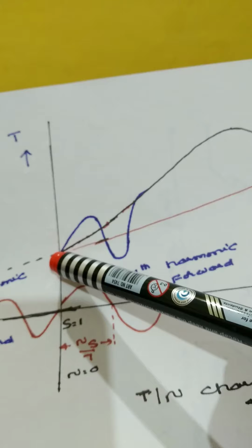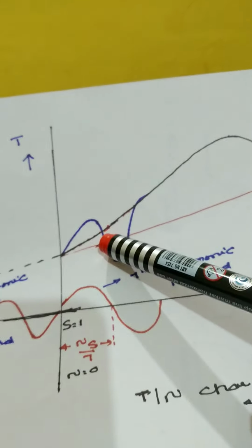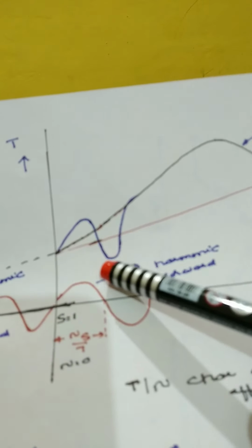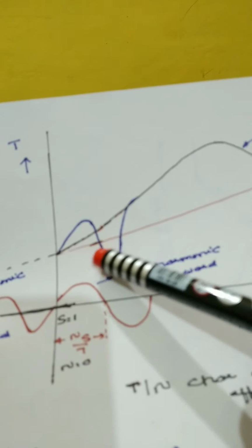And this is the motor torque, and the load curve here is less than this, so it will start. And if you analyze up to this point, TL is equal to TM, the motor still drives it. But after this point, physically, motor torque decreases, so it is not able to drive the load.